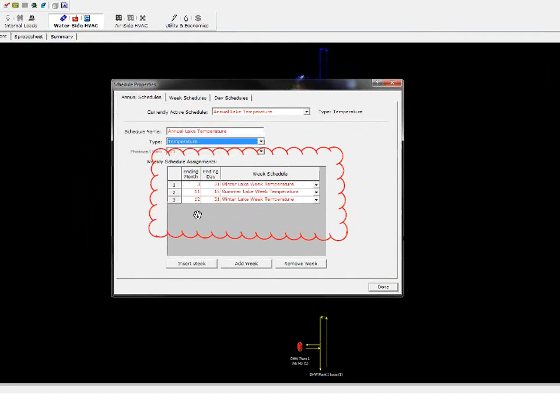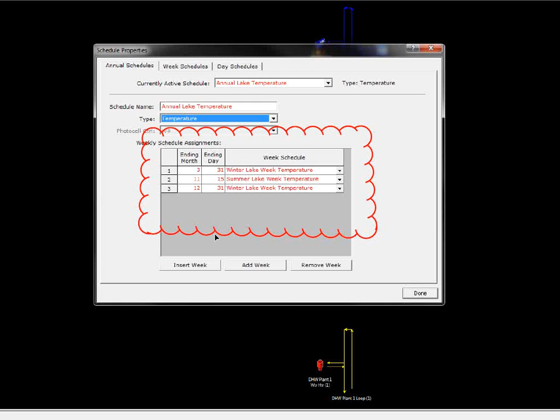So, Rick, just some clarification on my part. The fact that the loop is either at 90 or 70 doesn't mean the entire building is heating or cooling. There is some ability for it to do both, right? Yeah. And again, I didn't verify, but I'm assuming from reading all that documentation on the loop-to-loop heat pump that's what it says it does. eQUEST is doing that. It has four different modes for the loop-to-loop: cooling only, heating only, cooling dominant, and heating dominant. When it's cooling dominant, it's rejecting heat into the condenser loop, and then the heating side, if needed, pulls it out. And it does say the efficiency of the chiller drops because the condenser loop water would be hotter coming back. Yeah, like I said, reading all that documentation, it seemed pretty much what I had going on.